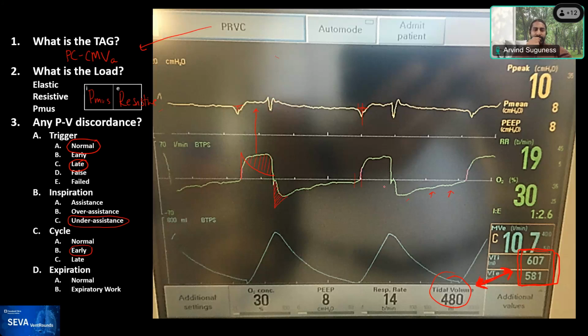Yeah, so what Dr. Mireles is drawing there is what you'd expect to see in a normal passive expiration: a sharp increase in expiratory flow, and then a gradual decay. But as you can see, the maximal expiratory flow is delayed here, and it doesn't reach that sharp peak. And that tells you that the patient's effort, like you said, continues into expiration. They're continuing to try and draw additional volume even once the ventilator ends the breath. All right, and then in expiration, is this normal or is there expiratory work?